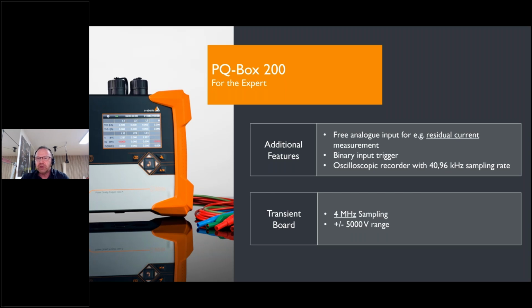So every time your machine has some disturbance, the PQ-Box makes a long disturbance record, and here it is a must that you have a lot of pre-time, not post-time, because in the end you get a trigger with the disturbance, and you want to know what happened in the grid in the time before. The fifth current input can be used to measure the current on the PE or a differential current, or if you do not need a fifth current, then we can connect here a temperature sensor or a sensor for sunlight radiation. We are really flexible here to connect any active sensor on the analog input.